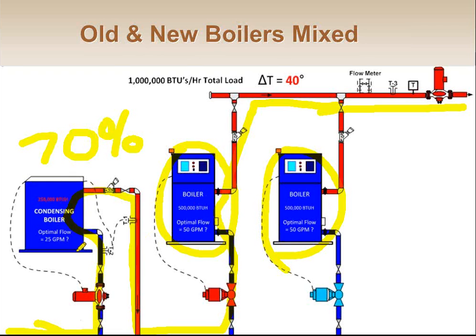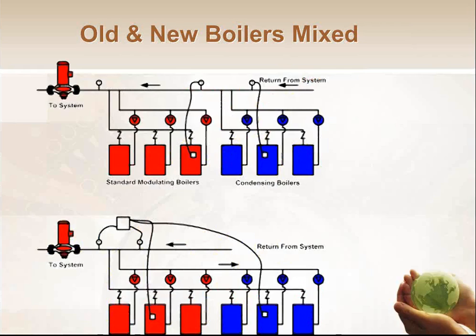The other nice thing about these condensing boilers is some of the ones we use have what we call the dinosaur switch on them. If he can't keep up with the load and make the set point, he closes the wiring to the dinosaur switch, which wires over there, and he's the go signal for the old boiler to turn on and help out. So that kind of makes the cost shock a little better for people, and they're more likely to actually replace or upgrade part of their plant than just replace it with an old efficient boiler. There's lots of ways to mix and match it.